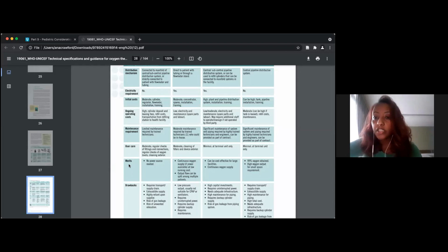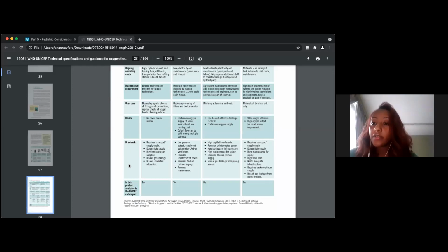When it comes to cost considerations, the initial cost is relatively moderate for oxygen cylinders and also for concentrators, but it's very high for liquid oxygen and oxygen plants. When it comes to ongoing costs, it's relatively high for oxygen cylinders because they need to be refilled and retransported from and to the institutions. For concentrators, the ongoing costs are relatively lower. Oxygen plants have relatively lower or moderate ongoing costs, and the same for liquid oxygen.